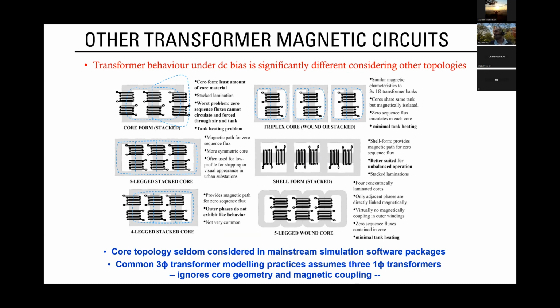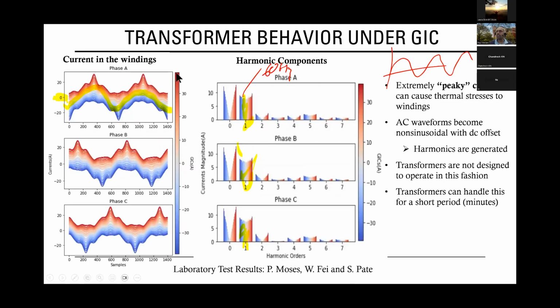So the question: what level of current was used in that test? I went up to about 40 amps of DC current. These transformers were small scale, smaller transformers, and we didn't dare go more than 40 amps because we didn't want to cause any accidents. We were pretty cautious when we did these tests because we didn't know what would happen. So we went 40 plus and 40 minus DC amps. In reality, on the bigger transformers, you can have hundreds of amps of DC.